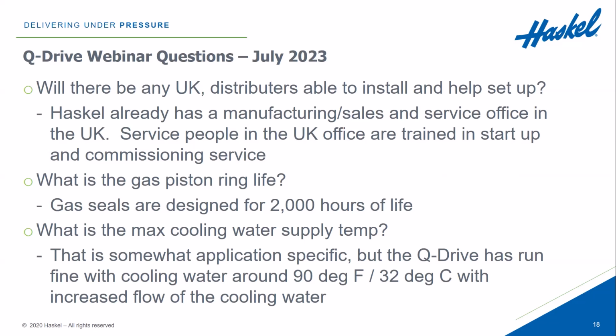What is the maximum cooling water supply temperature? I mentioned this earlier, but it's going to depend on your application, but around 85, 90 degrees Fahrenheit, 30, 32 degrees C. The warmer the water or coolant is, the higher the flow rate we're going to need through the unit to remove the heat that's generated.